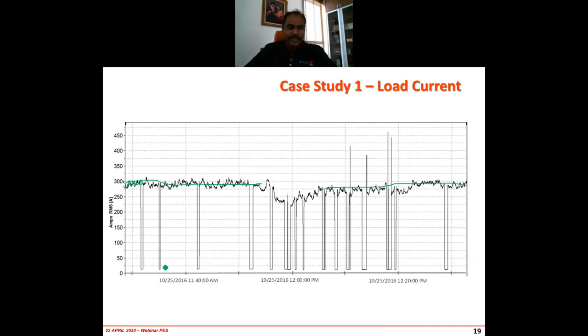But of course, sometimes it drops to about 14 or 15 amps. Why does it drop? Because when they see some issue with the product, they automatically give an instruction for the clutch to disengage. That means the motor will be running without load, and we see the current drop to about 14 amps. Then again, when the clutch is engaged, it shoots up to more or less 290 amps. That means the load is actually a constant load. The drop to 14 is because there's some defect in the output because of the soil moisture and so on. So more or less, it's a constant load.